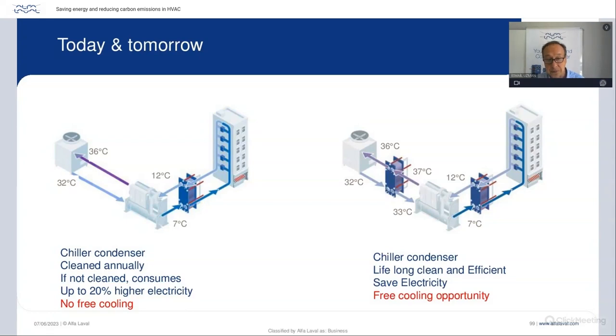higher electricity costs. Now, what we're suggesting as a savings for the HVAC industry is to put a plate heat exchanger between the chiller condenser and the cooling tower. What will happen is that the condenser will receive 1 degree Celsius higher cooling water temperature. Whatever the cooling tower water is, the condenser will receive 1 degree higher. But the good thing is that this loop between the condenser and the heat exchanger is lifelong clean, and the condenser never loses efficiency due to calcium carbonate. So we have an opportunity to save electricity on the condenser and also to allow for free cooling.